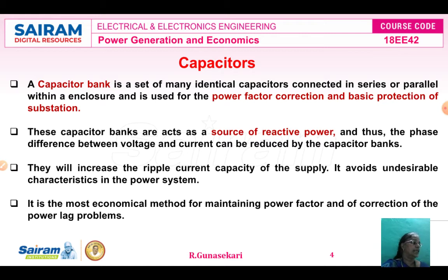The shunt capacitors are used for compensating reactive power of the lagging power factor, for improving the power factor, and for voltage control during heavy lagging power factor loads. The shunt capacitors are located at the receiving stations and distribution substations. Shunt capacitors are switched in during heavy loads and switched off during low loads.